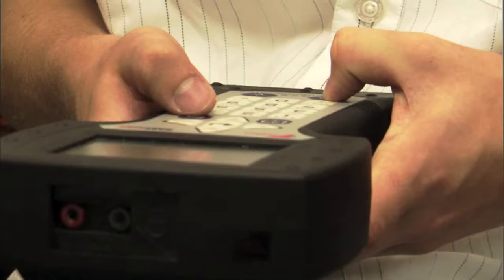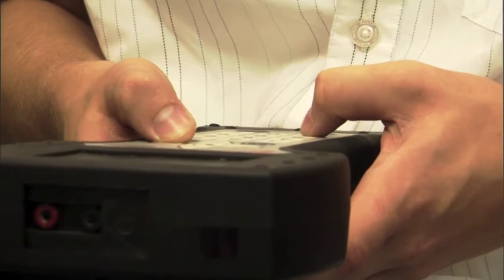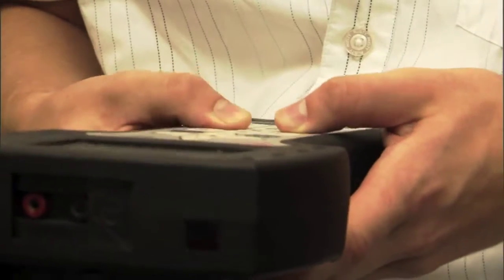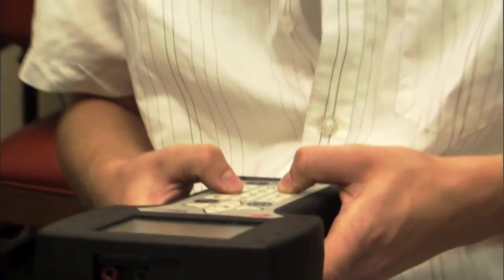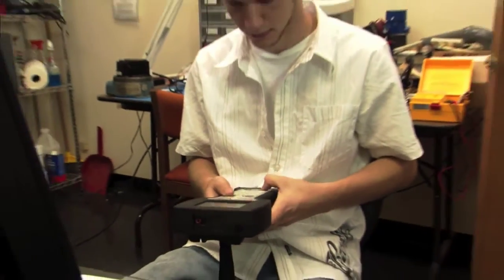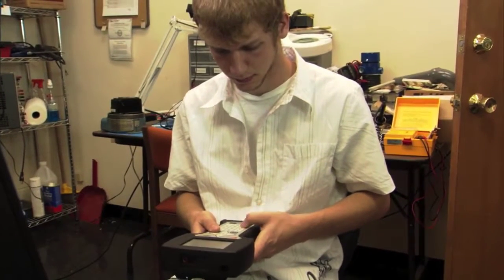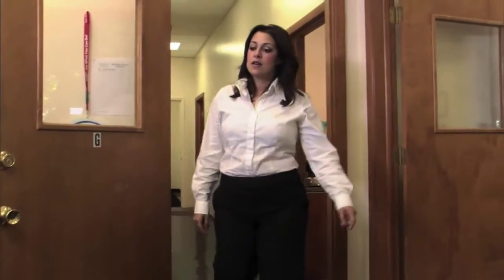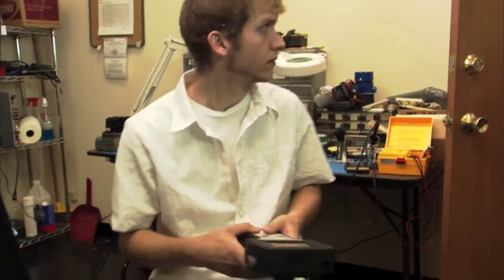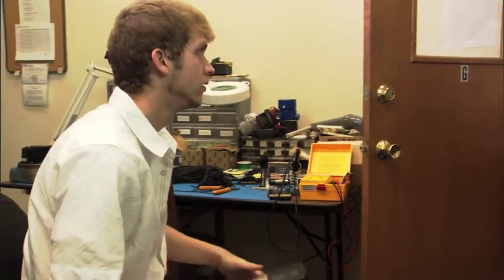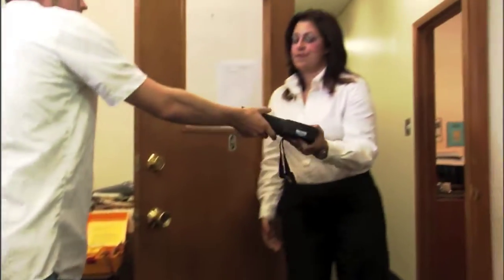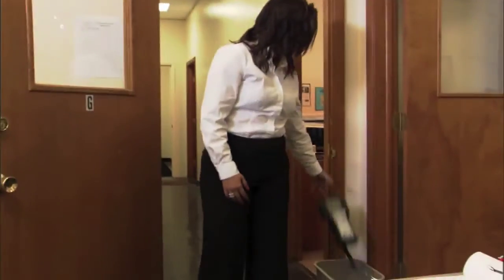Some HART communicators and software packages do not use the compiled DD binary file in their communicator or software. They modify the format. This can cause problems because the modified format has not been tested by the device manufacturer. This can also create a lag between the time a new DD is released and when modifications are finally added to their HART communicator or software package.